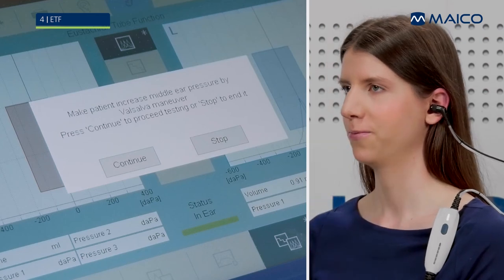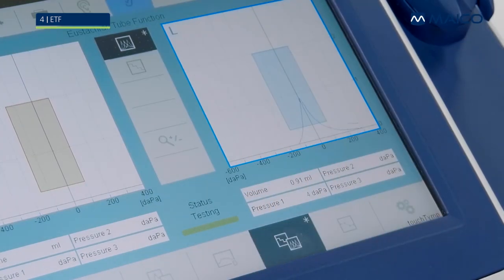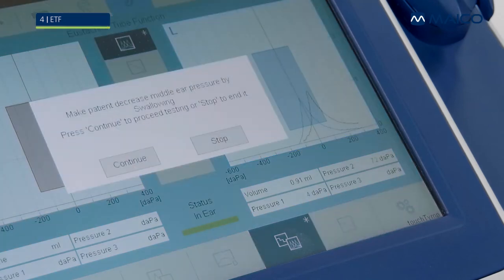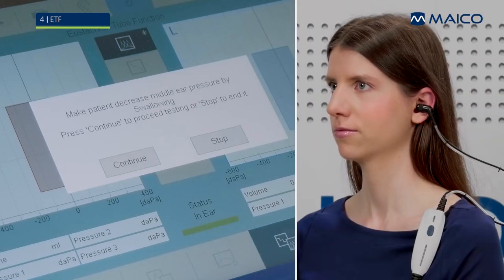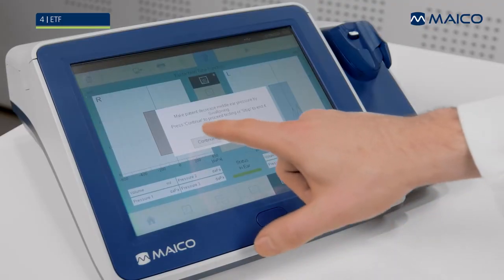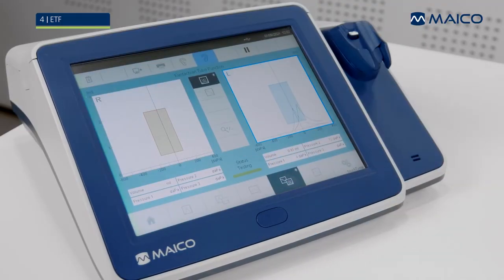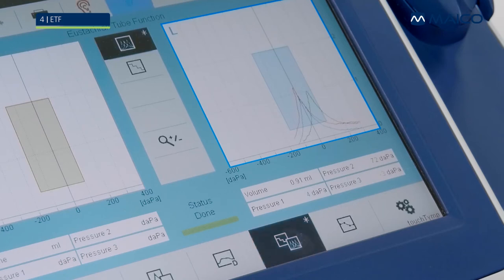When completed, press Continue to proceed to the second tympanogram. The pressure at the maximum compliance appears under pressure 2. Following the measurement, another instruction is displayed to have the patient perform the remaining second maneuver. Press Continue to perform the third tympanogram. The pressure at the maximum compliance displays under pressure 3.